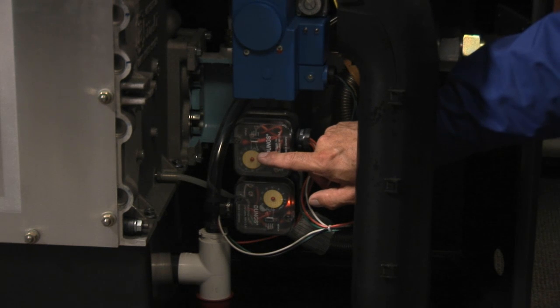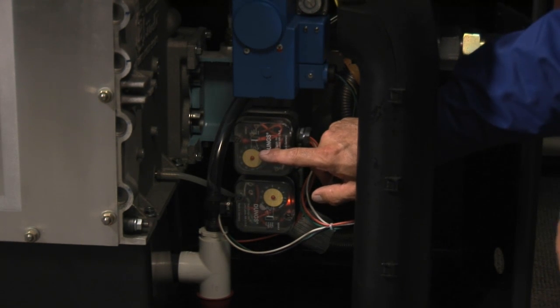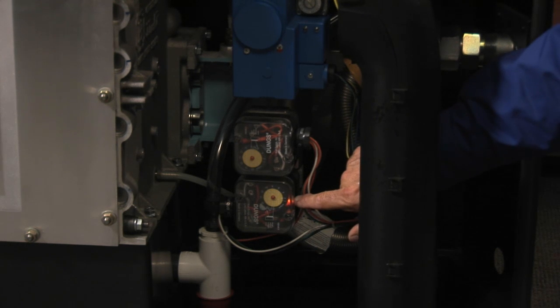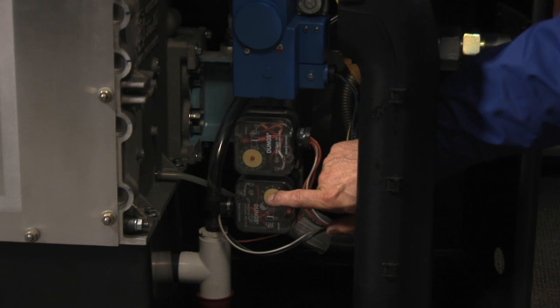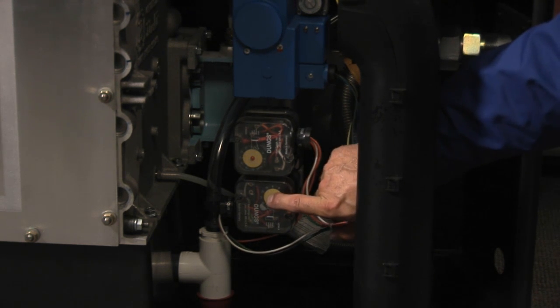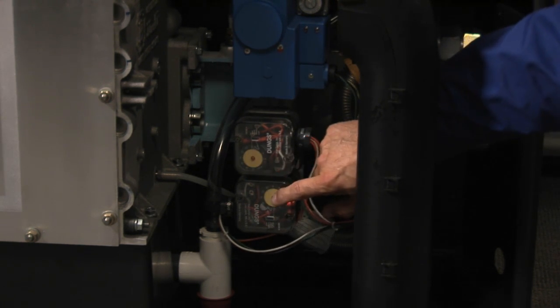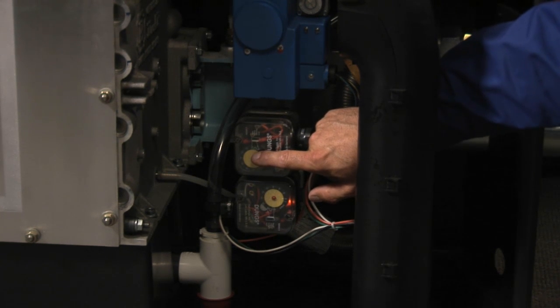These are 120 volt high and low pressure gas switches. They're adjustable. And if they happen to go out on high or low pressure, as you can see here, there's a little LED light right now that's on. We have low gas pressure. And they are resettable right here with the cover on. You just push this little red button on the low pressure or the high pressure switch, and you can reset the control.